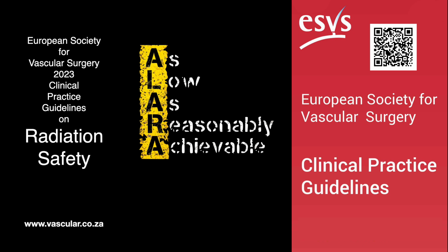So the recommendation leans towards fixed systems. Yes. Recommendation 23 is Class 2A, Level C. An endovascular operating room with a fixed imaging system should be considered over a mobile C-arm, particularly for optimizing imaging quality and reducing operator exposure through integrated shielding. What about controlling the imaging, operator-controlled imaging, OCI?